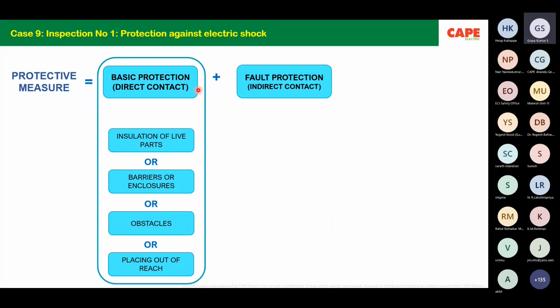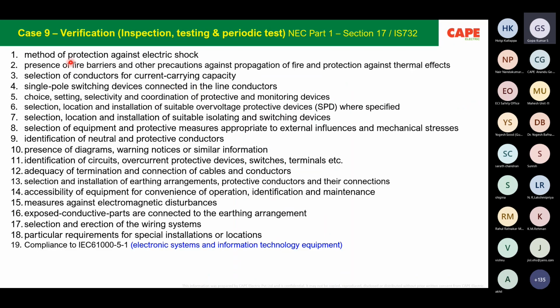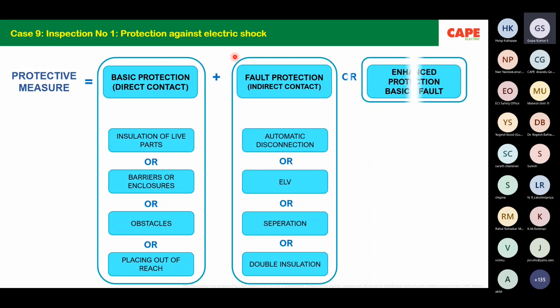So for verification, the inspection part 1 in the previous slide, the method of protection against electric shock: the inspector should be aware of these protective measures, their applicability, their locations, where they are. For example, in a wet area, you may have to have one more protective measure. So the inspector should be aware of it, and has to check whether these protective measures are appropriately applied in these areas. Like that, there are 18 or 19 inspections included in the standard.